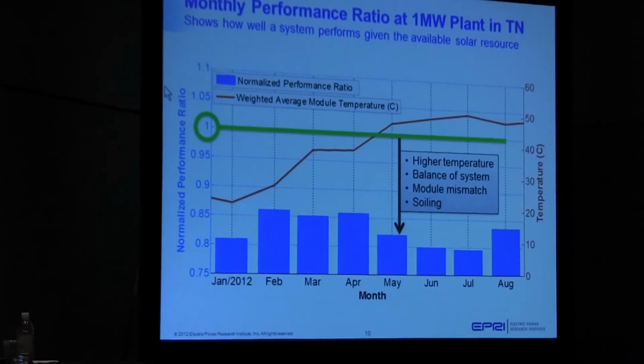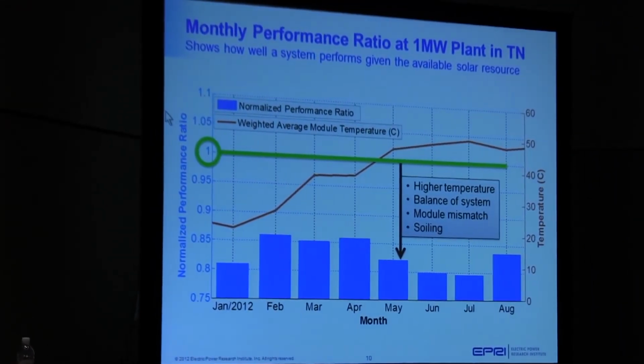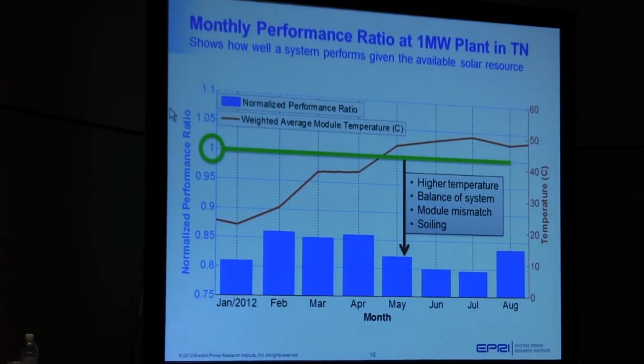And it's a useful metric to compare relative performance if you're looking at month by month, or if you have different types of systems in the same region, you can see how they're performing relative to each other. So a ratio of 1.0 means I'm operating perfectly, and you may never ever see that, because you have inverter losses, balance of system losses, module mismatch, etc. So let's look at the graph. From the eight months, you can see we're dancing around in the low 80s on our performance ratio. The green line is our golden egg there. It's our 1.0 target, and the decrease from that is really essentially how you would derate the system if you were planning for it.